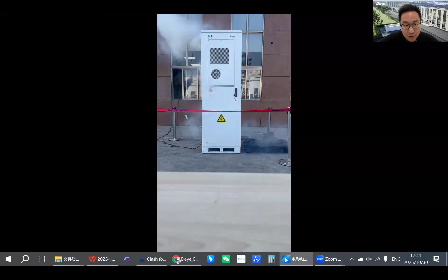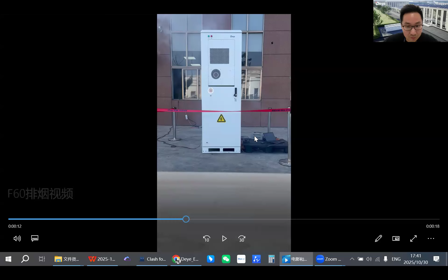As you can see, we manually triggered thermal runaway inside the F60. What just happened is there's an exhaust port and an air intake similar to the 215, pulling in fresh air, with an exhaust port on top extracting fumes outside the cabinet to prevent explosion.